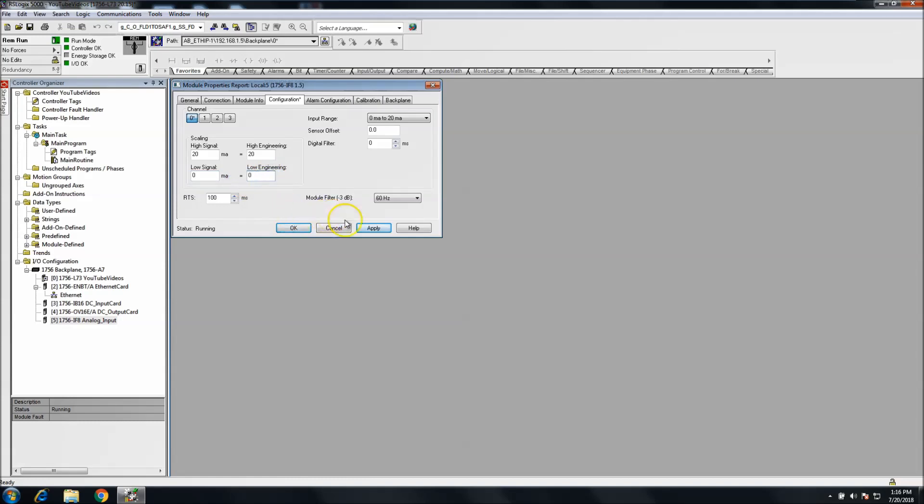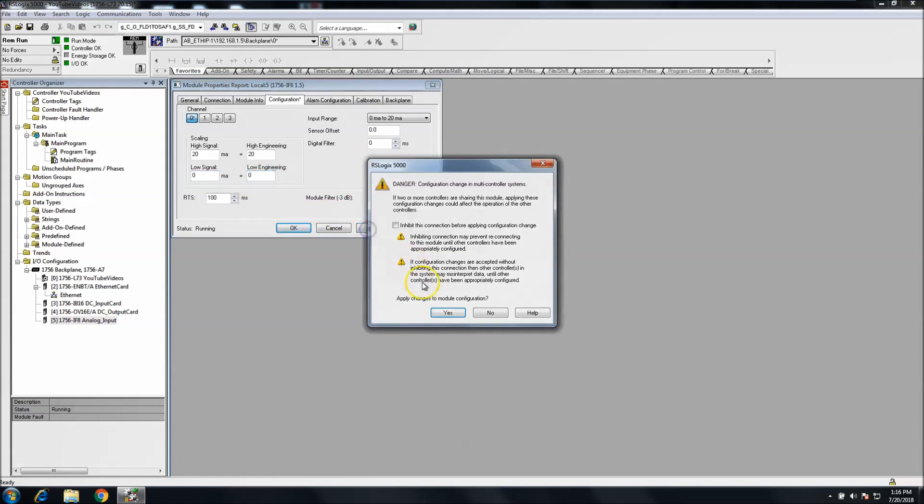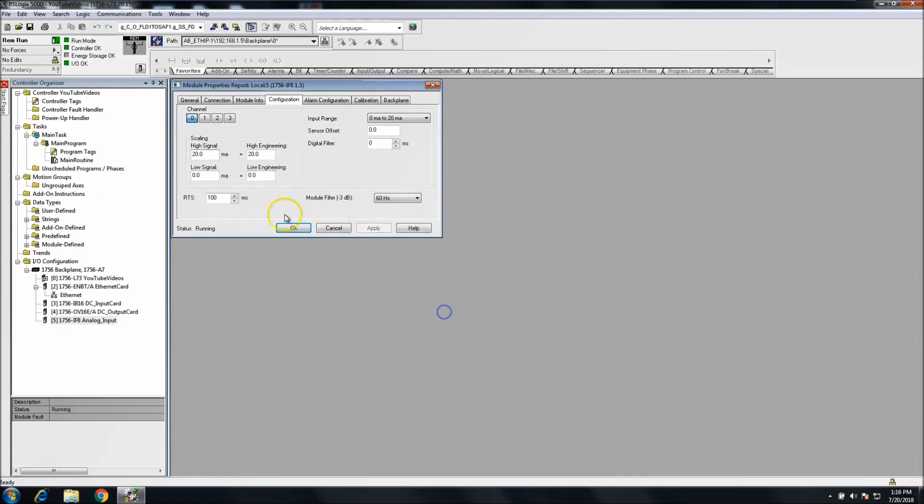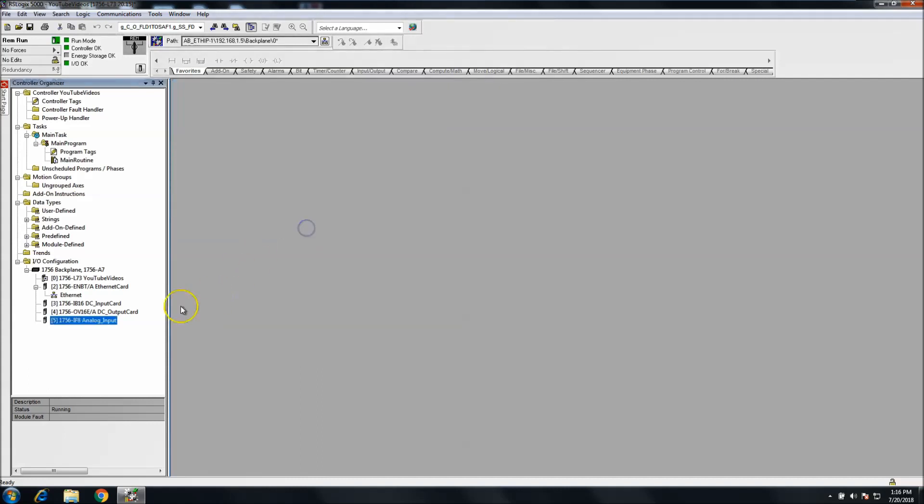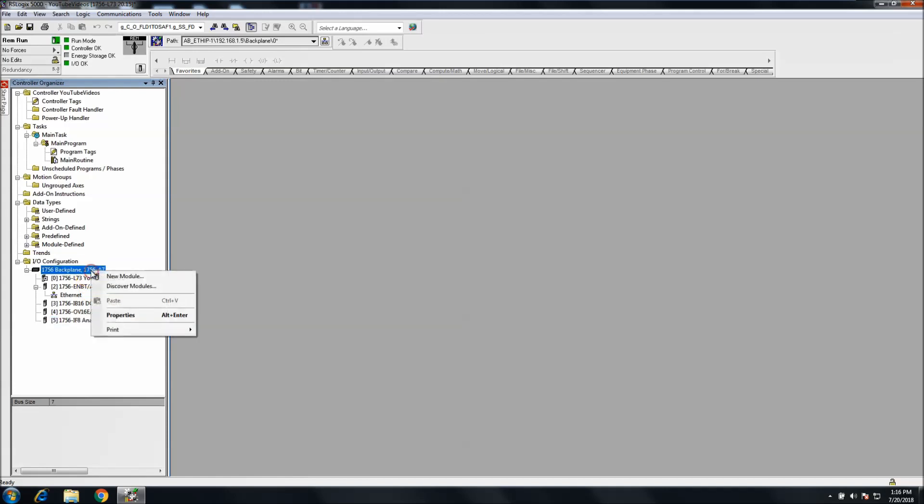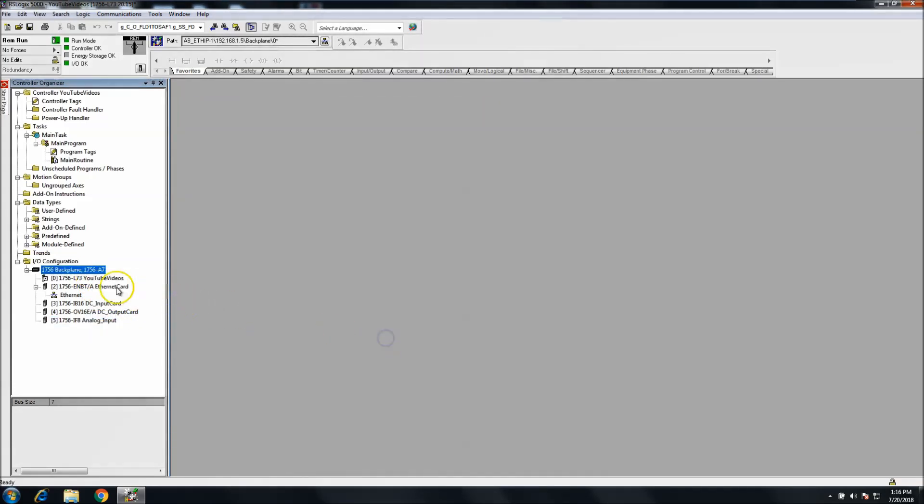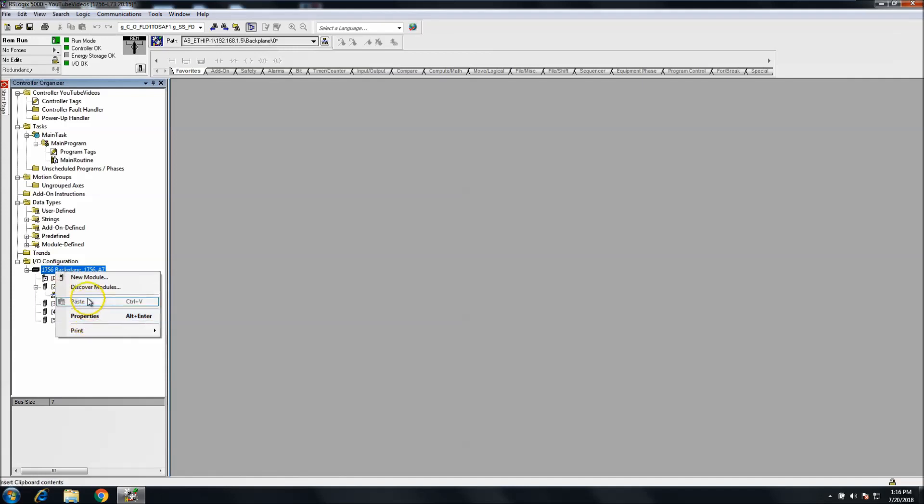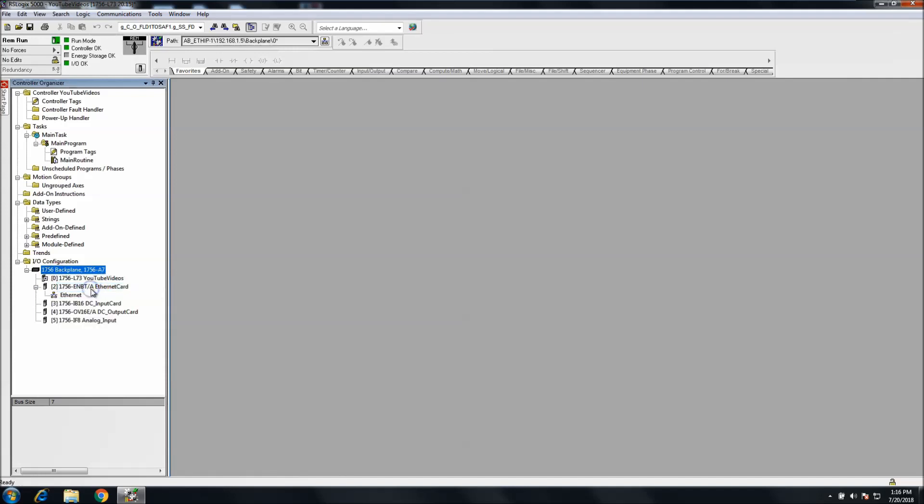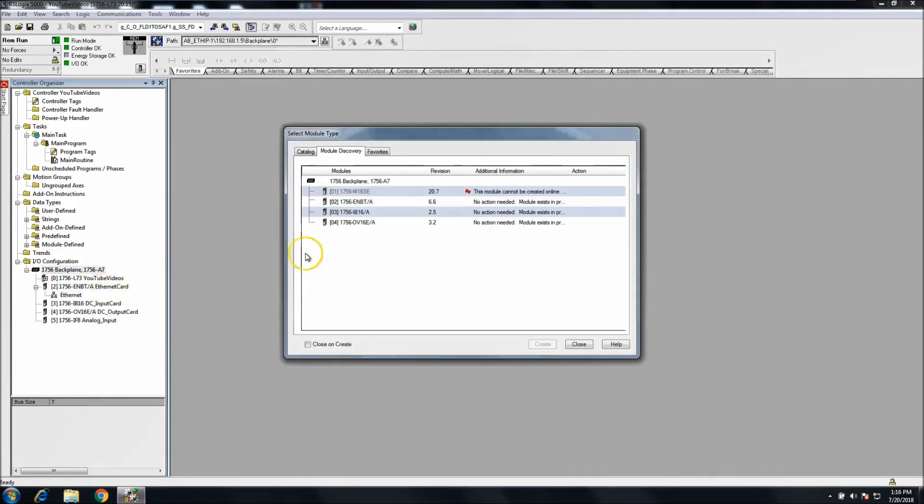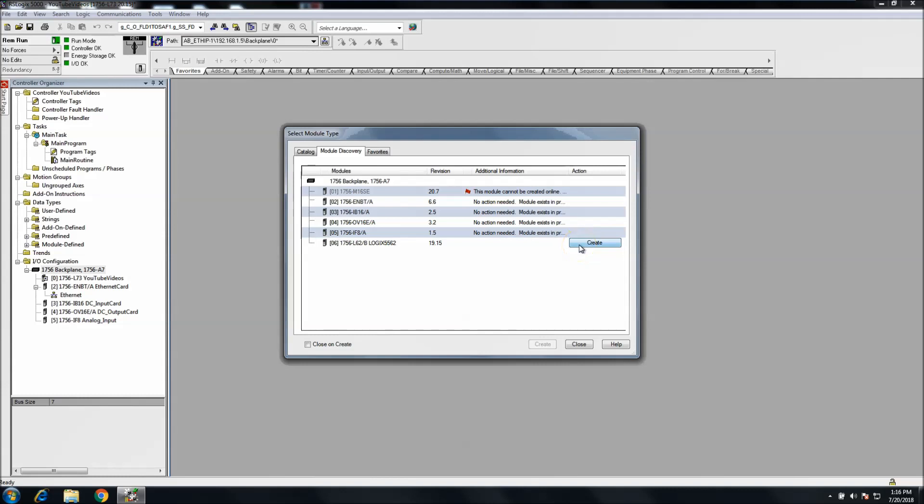Then when I change my engineering units to match, it will accept it. So now that actual channel is four to twenty, and this is a four channel card, so I would have to do that on each one of these. Just another thing for you to understand is it's not going to pull in general information. It's not going to pull in exactly what you want. It doesn't know necessarily how your setup, how you're choosing to use your setup.